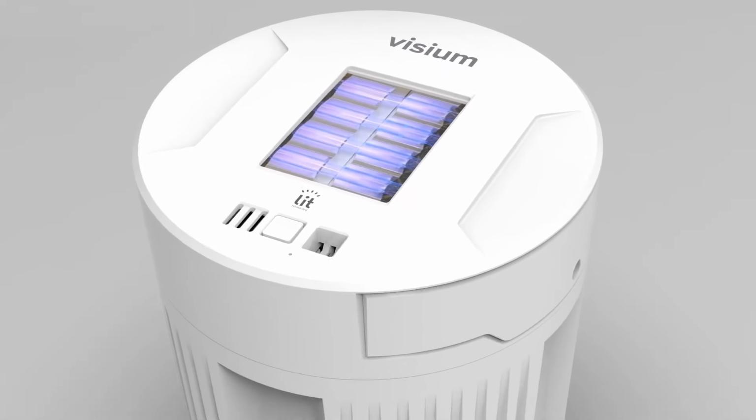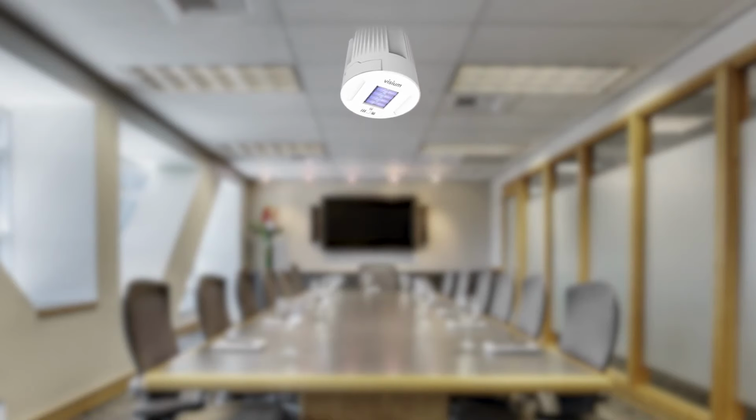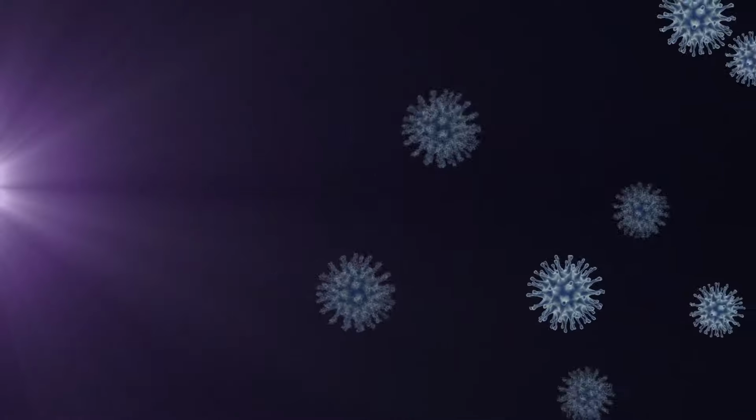It's silent, but what it does is it emits filtered UV light at a specific wavelength, 222 nanometers. That's somewhere in between 200 and 230 nanometers, which is that effective wavelength. And that is highly effective against the DNA and also the protein layers on simple viruses, simple bacteria, but it's very, very safe for humans. So what you get is this magic that turns science on its head, that finally we've got something that's effective against pathogens that are so destructive, and we can do it in an occupied room without having to use sunglasses and sunscreen, just like you do out in the sunshine. So that's really the nub of it, that it's an amazing technology that the world hasn't woken up to yet.